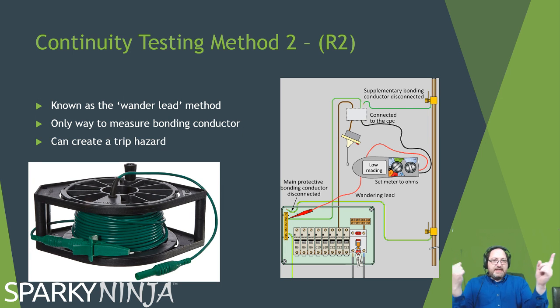Because our test leads are only so long, a meter or two, we'll zero out this test lead, plus we'll zero out this long wander lead, which could be anything up to an ohm. And then we'll run the wander lead out from the board, crocked onto the disconnected earth, and at the other end we'll just test from the port on the wander lead to the exposed conductive part, or whatever the earth is that we're testing to. Okay? It's a very effective way of testing light switch drops or metal containment. It's the only way you can verify bonding, because there is no line conductor to bonding. The problem with it is it does create a bit of a working difficulty with safe working because of the trip hazard. But it's a good way to fly around and collect information quickly if you can control the work safely.